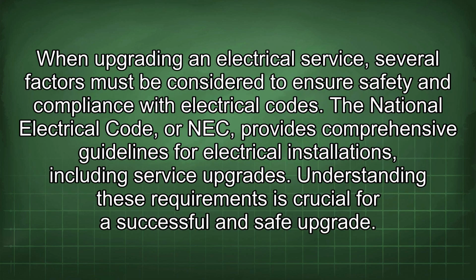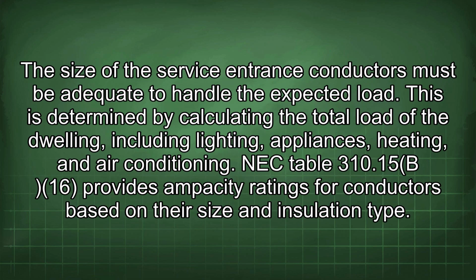When upgrading an electrical service, several factors must be considered to ensure safety and compliance with electrical codes. The National Electrical Code, or NEC, provides comprehensive guidelines for electrical installations, including service upgrades. Understanding these requirements is crucial for a successful and safe upgrade. The size of the service entrance conductors must be adequate to handle the expected load. This is determined by calculating the total load of the dwelling, including lighting, appliances, heating, and air conditioning.